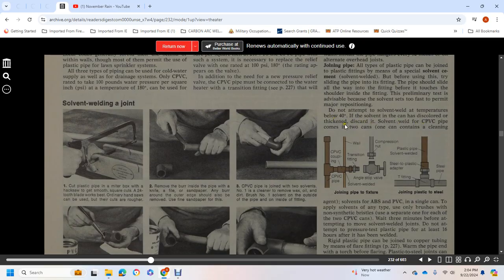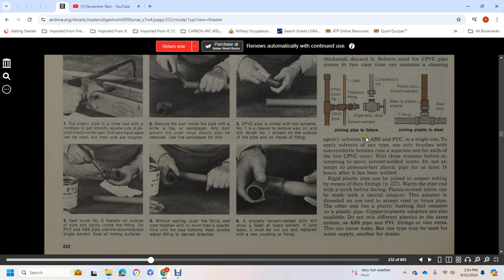Solvent for CPVC comes in two cans. One can contains cleaning agent. Solvent for ABS and PVC comes in a single can. Apply solvent to any type using only brushes with non-synthetic bristles, a separate one for each of the two CPVC cans. Wait 3 minutes before attempting to move the solvent welded joints. Do not attempt to pressure test plastic pipe for at least 16 hours after it has been welded.